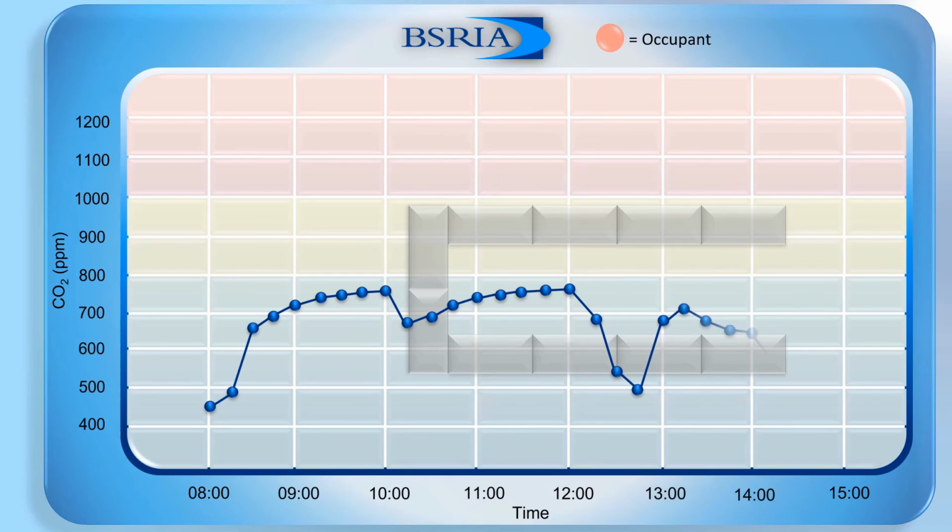When the meeting ended, everyone left the space and the decay of the CO2 concentration follows a standard decay due to the ventilation rate within the space. This is entirely based on the peak CO2 of when everyone left and the ventilation rate at the time.